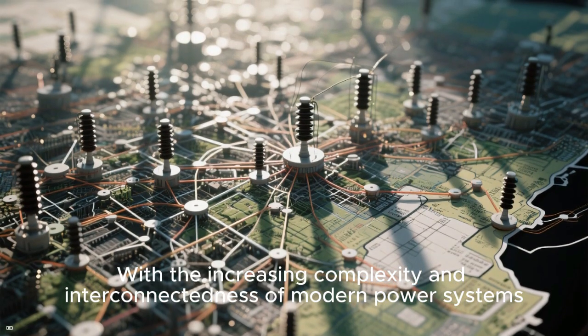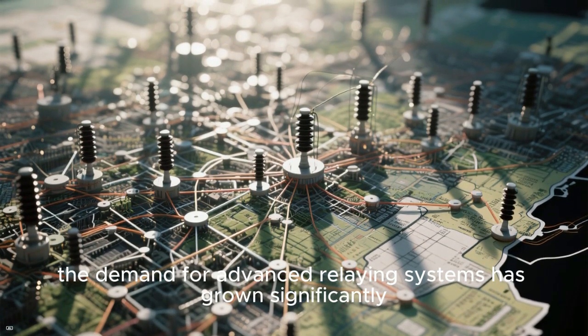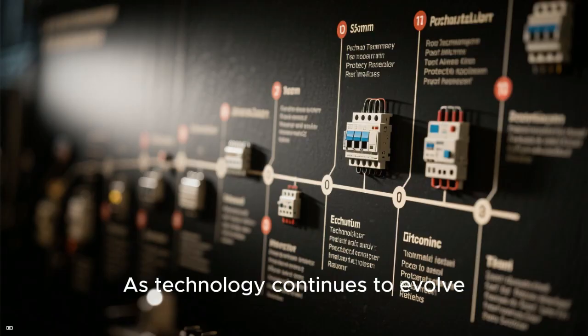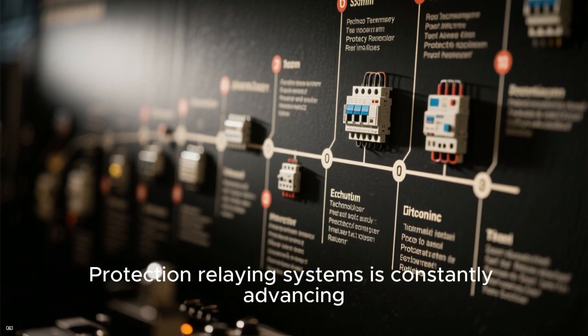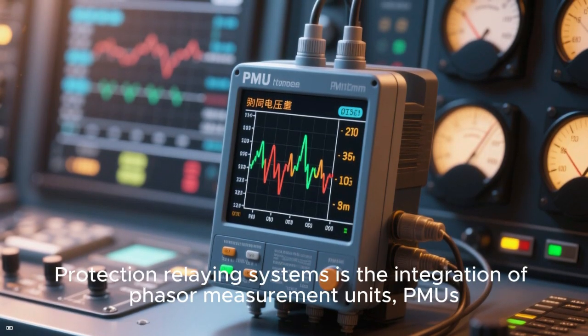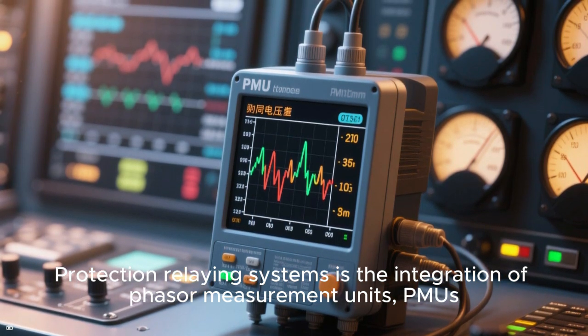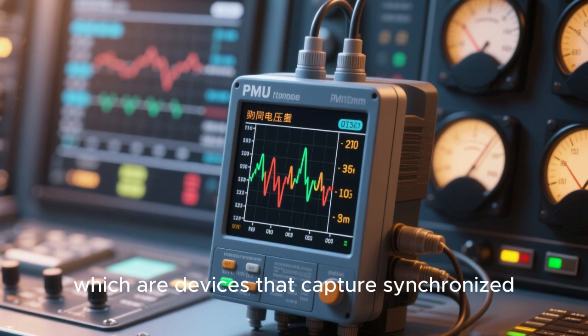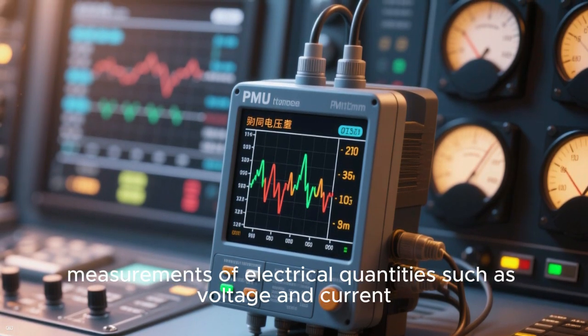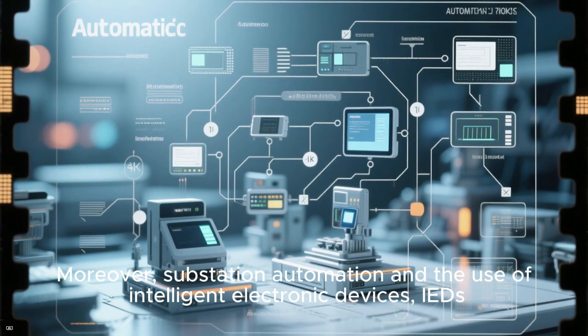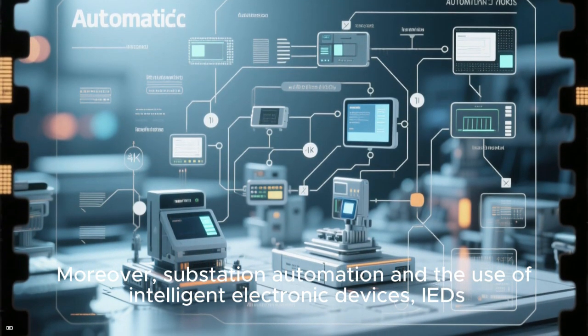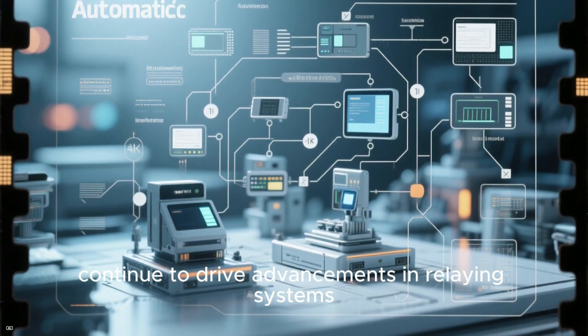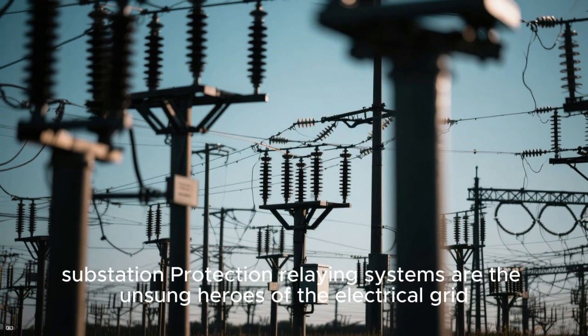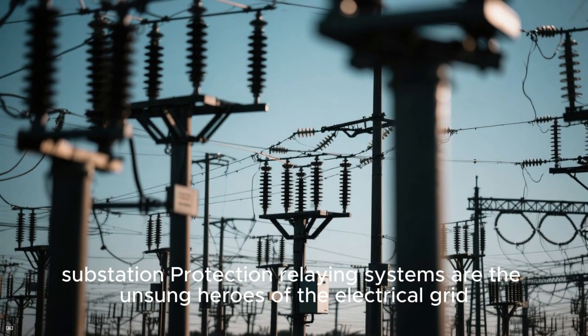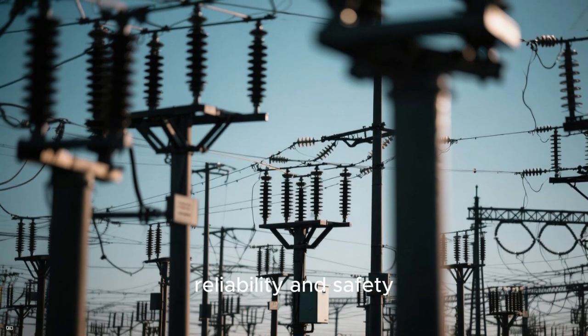With the increasing complexity and interconnectedness of modern power systems, the demand for advanced relaying systems has grown significantly. As technology continues to evolve, the field of substation protection relaying systems is constantly advancing. Another exciting development is the integration of phasor measurement units, PMUs, which are devices that capture synchronized measurements of electrical quantities such as voltage and current. Moreover, substation automation and the use of intelligent electronic devices, IEDs, continue to drive advancements in relaying systems. In conclusion, substation protection relaying systems are the unsung heroes of the electrical grid, ensuring its stability, reliability, and safety.